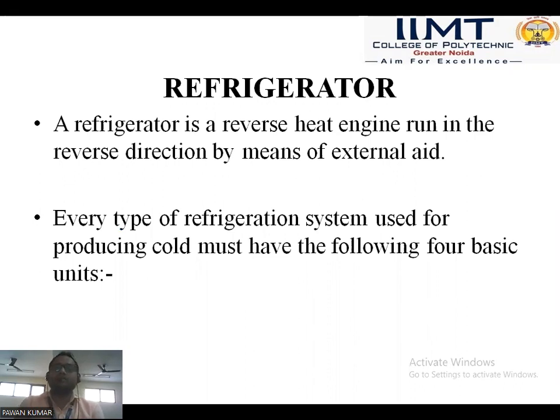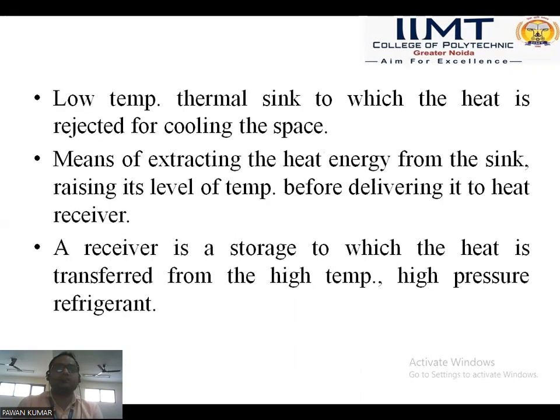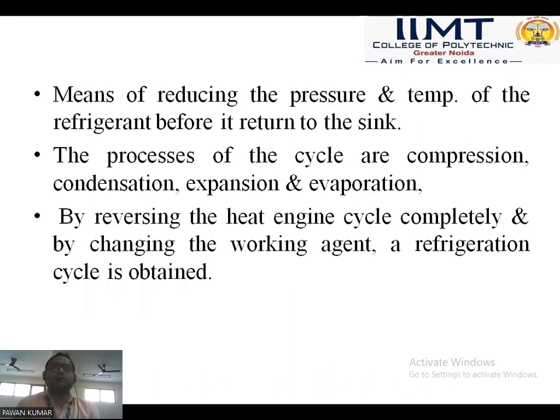What are the basic components available in each refrigeration unit? First, a low temperature thermal sink. Next is the means of extracting the heat energy from the sink and raising its temperature before delivering the heat. A receiver is a storage to which the heat is transferred from the high temperature, high pressure refrigerant. Another is the means of reducing the pressure and temperature of the refrigerant before it returns to the sink. To remove heat we use the condenser, and to reduce the pressure we use the expansion device.